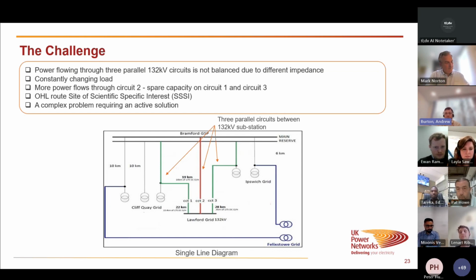We also had consistently changing load. On each of the feeders there were different types of distributed generation, so the load was constantly changing. Upon investigation, we identified that power flows were high through circuit 2, but there was spare capacity on circuits 1 and 3.